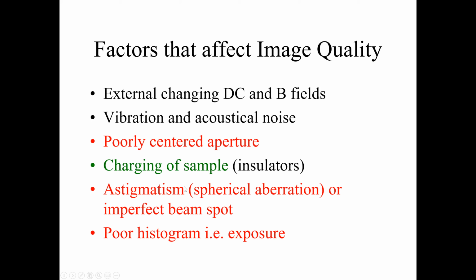When you get into these multiple corrected microscopes, you're talking well over 1 million compared to 100,000. You really can't do much with the astigmatism. All you can do is change out the aperture and keep it clean and try to center it the best you can. But the size of the beam spot really depends on how the magnetic column's set up in the microscope, and that's on the manufacturing end. You just can't go in there and fix it. You just can't buy an add-on that'll fix it.